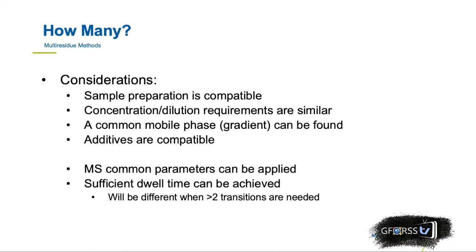Now comes the concept of dwell time. Dwell time is the amount of time that the mass spectrometer spends accumulating data. We usually report dwell time and resulting points per peak, where a minimum of 10 to 15 points per peak is preferred. During the period of accumulation of the information, the dwell time, the signal is averaged, but so is the noise. This results in an increased signal-to-noise ratio since the noise is random and will add and subtract, while the signal should always be about the same.